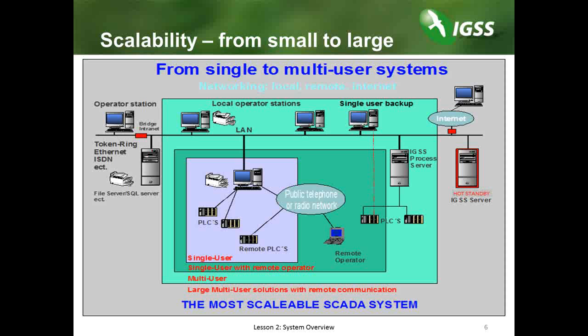As the process grows larger, more operator systems and stations can be added. An IGSS server becomes necessary if the process expands into a multi-user system, as depicted in the light green area. A multi-user system is defined as a system with one or more operator stations and requires a server to be set up. As a side note, an operator machine can be configured to connect as a multi-user but set up to continue gathering data in case of a server outage. When the server goes online again, the collected data is synchronized back to the server — this is called a single user backup operator.